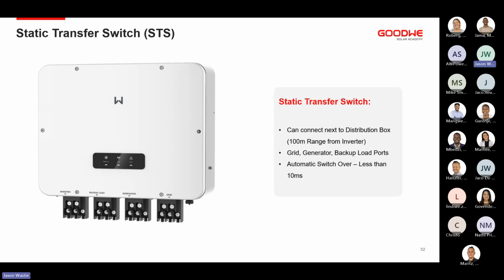The STS has also got generator, backup, and grid load ports, with the generator port also being able to double up as a big load port if needed. The STS also supports up to 138 kilowatts and 200 amp output through the STS, meaning it's quite robust and won't bottleneck from the inverter to your loads.